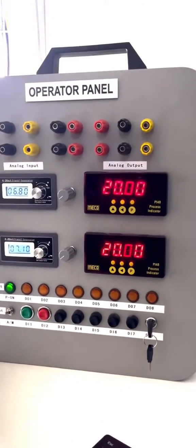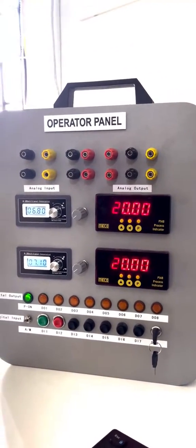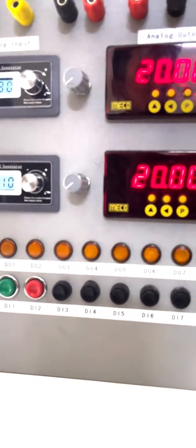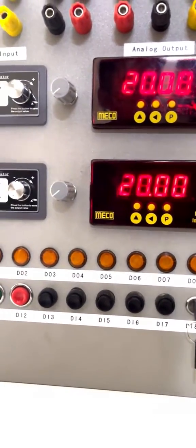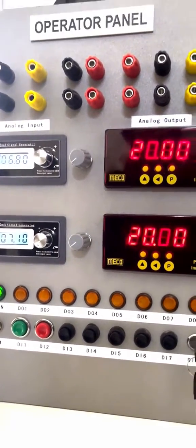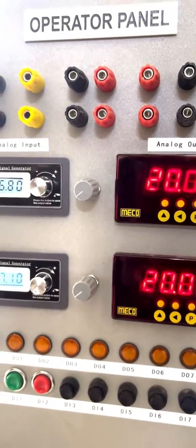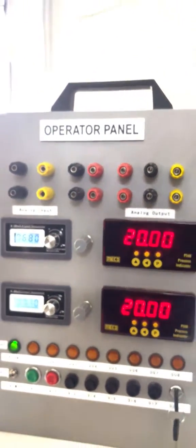In addition to that, we have connected the IOs to a real-time operator panel where you will be able to have hands-on experience with the IOs. Here we have connected the digital inputs to the push buttons and toggle switches, and we have connected the digital outputs to the lamps in the operator panel. We also have a 4 to 20 milliamp signal generator for analog input configuration and a display to show the analog values.